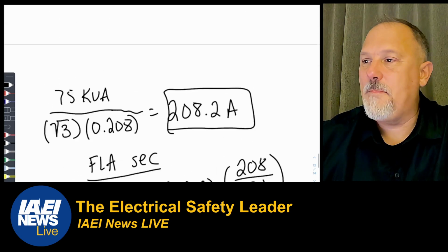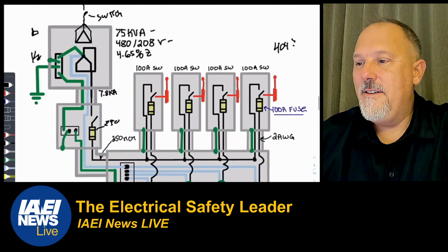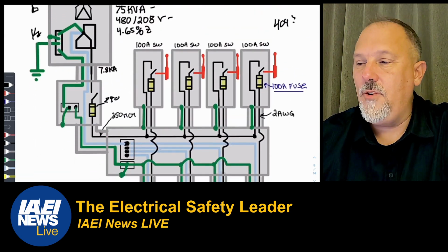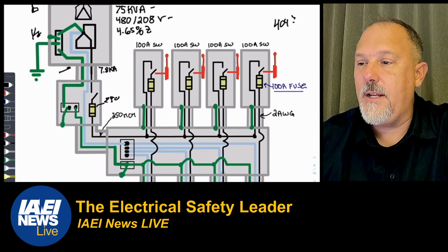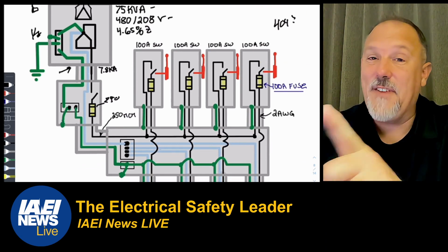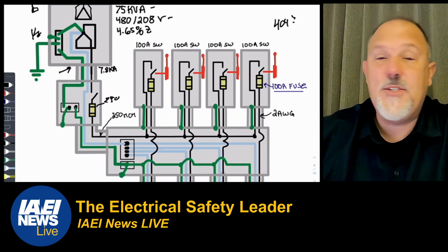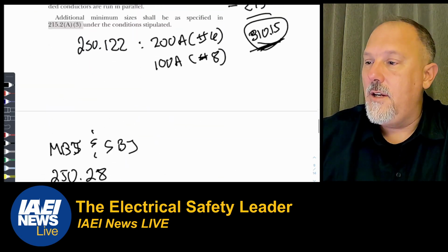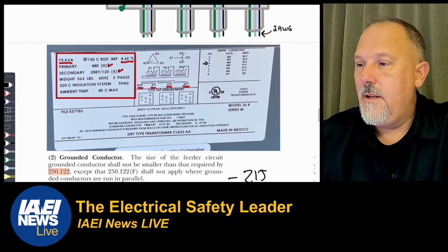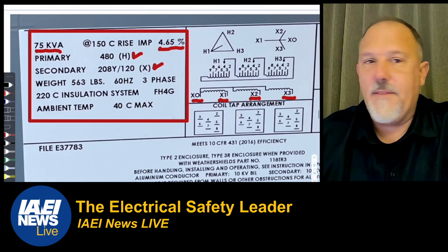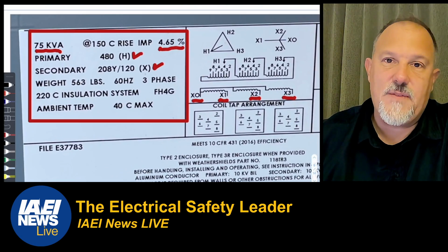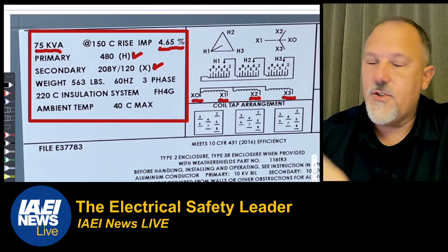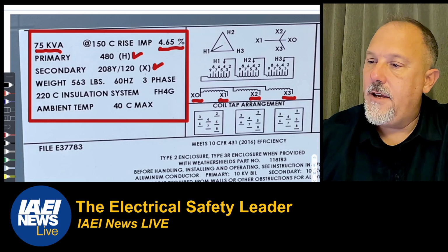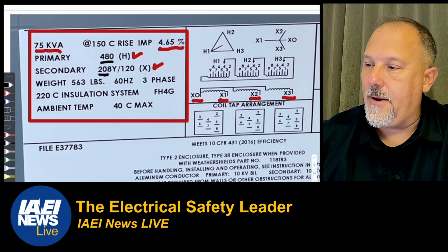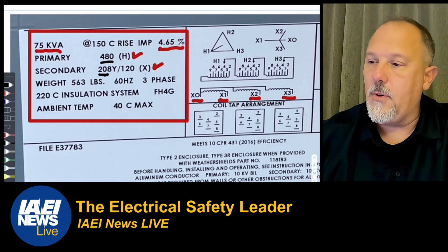Now the next piece of information that you could use as the starting point here is the available short circuit current. So how do I do an infinite bus calculation? What was the impedance? So there's your data. I've got a 75 kVA, 4.65% impedance. So remember that number, 4.65. There's my voltages on a primary and secondary. Those are the important information that you need.